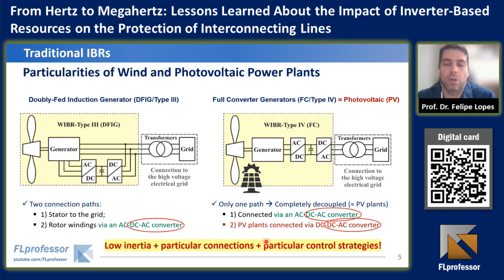We noticed that there is a low inertia because these generators do not have huge mass to maintain an operation point, and the mechanical time constants were replaced by the control time constants, which are much faster than the mechanical ones. We understood that there is a low inertia to deal with. And due to these particular connections, we realized that particular control strategies and behaviors during faults were also an important aspect to be understood.